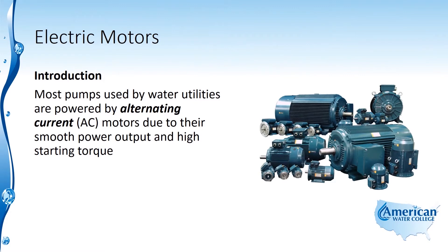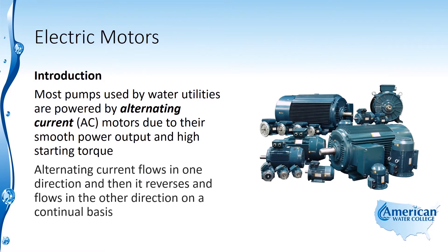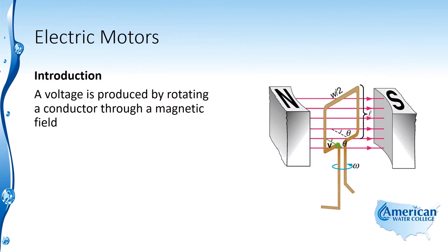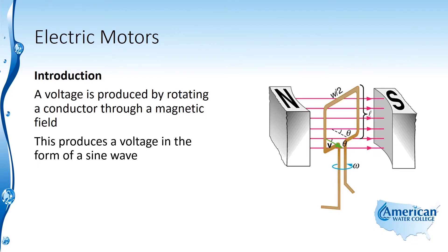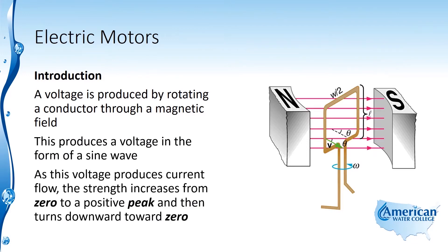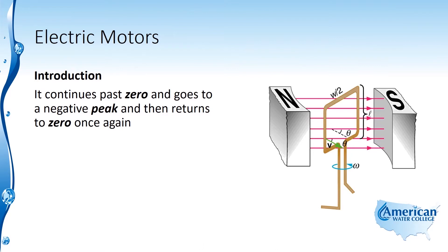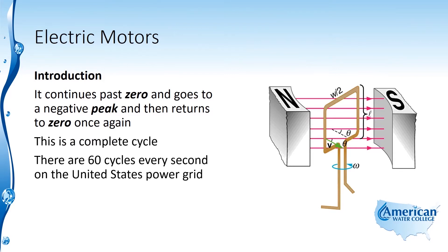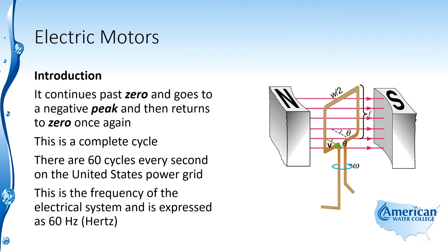Most pumps used by water utilities are powered by alternating current motors due to their smooth power output and high starting torque. Alternating current flows in one direction and then reverses and flows in the other direction on a continual basis. A voltage is produced by rotating a conductor through a magnetic field, producing a voltage in the form of a sine wave. The strength increases from zero to a positive peak, then downward to zero, continues to a negative peak, and returns to zero — completing one cycle. There are 60 cycles every second on the United States power grid, expressed as 60 Hertz.